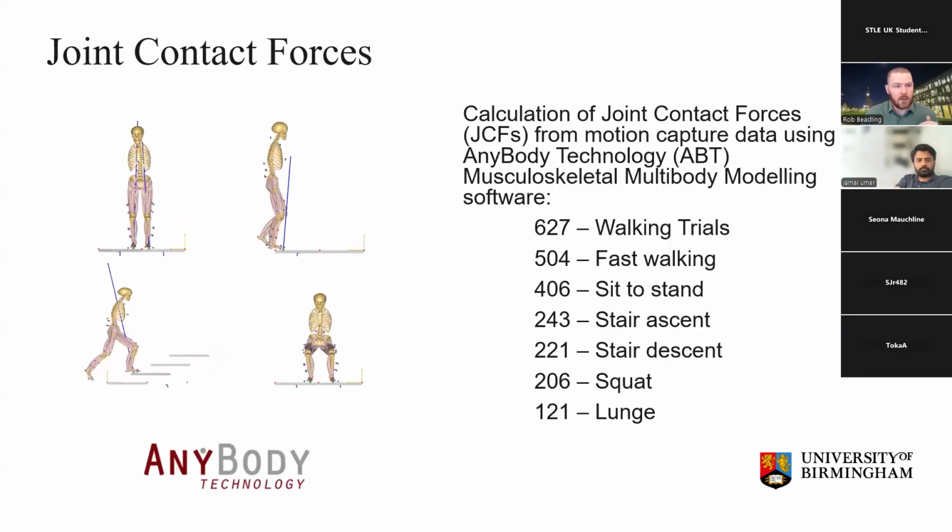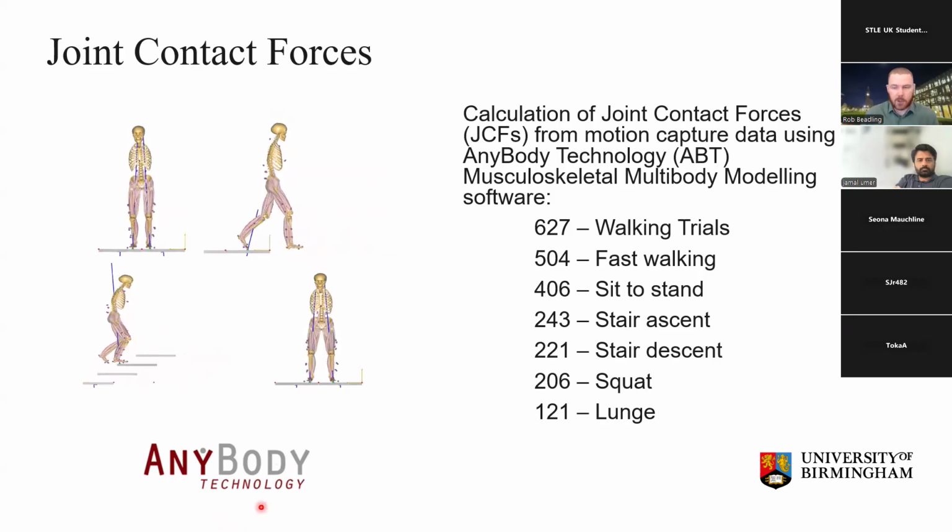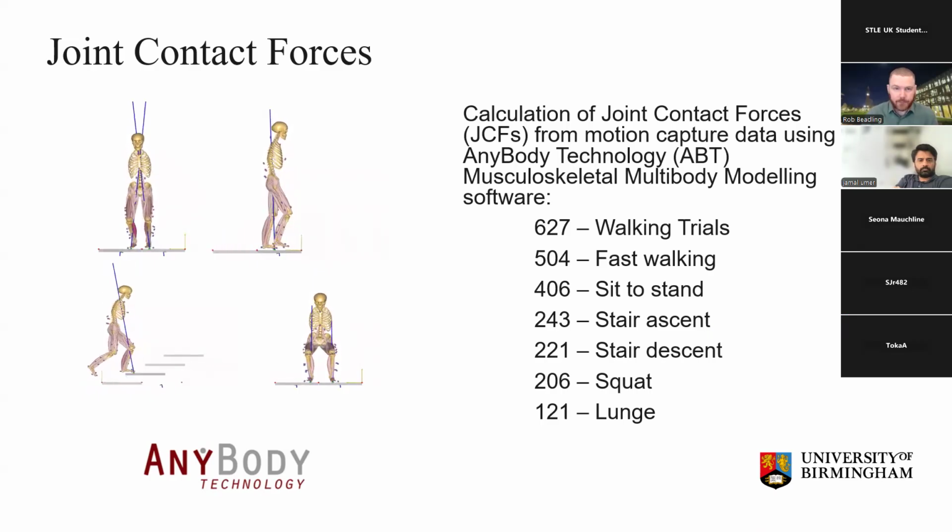We can run this motion capture through musculoskeletal body modeling. So this was in collaboration with AnyBody Tech, where we can take those motion capture trials and develop joint contact forces and profiles to put on the simulator, that kind of, rather than, again, just that continuous walking, we can run devices through a day in the life of the patient or a week in the life of the patient. And we can do that for different patient classes.